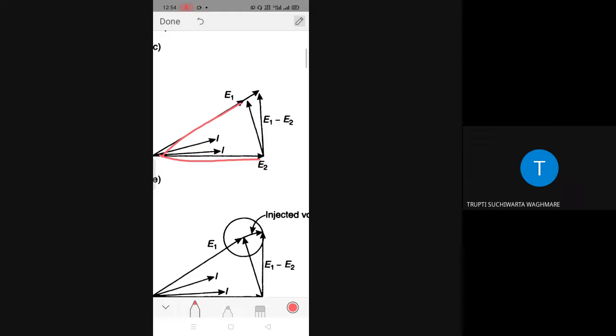The second one, as I said, X is done. Next is the magnitude of E. Please stick to this equation: how we are playing with X, delta, E1, E2. Now here we have the earlier curve, E1, E2, its difference EL, and according to that the current is this. Now suppose at one end of the line, say end 1, I add some shunt compensator like a voltage regulator and change the magnitude of the E1 bus voltage. I increased the voltage magnitude at the bus 1 end of the line. Now with this increase in voltage, what happened? The difference between E1 and E2 changes, but that change in magnitude is very slight. If you look at this magnitude and that magnitude, there is a slight change in the magnitude of the voltage drop across the transmission line.